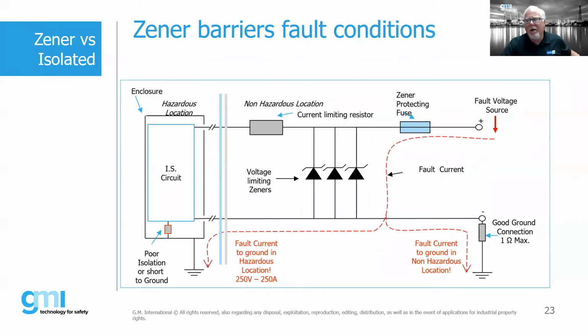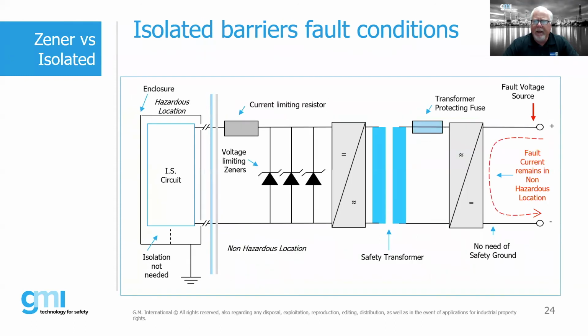So with a Zener barrier under a fault condition, if we didn't have a good ground, or even if it somehow passes over to the normal earth, we have that fault in the hazardous location. The grounding issue is usually our biggest issue with regards to the use of Zener barriers. So that's why the good ground, the dedicated earth, is so important. And again, the same thing happens in an isolated barrier. Again, we don't have to have that safety ground.